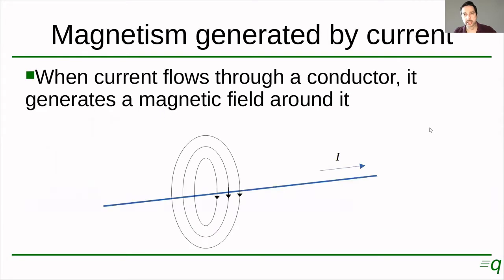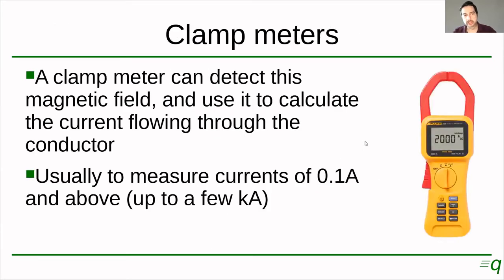So let's start with electricity and magnetism. Magnetism can be generated by current flowing through a wire. In this case we have a wire here and these lines represent the magnetic field that this current creates when it flows. Now we can take advantage of that magnetic field and measure it with a specific device. So if we build an instrument that has a magnetic sensor, and knowing that the magnetic field increases when the current increases through the conductor, we could calculate how much current is flowing through the conductor by measuring the magnetic field.